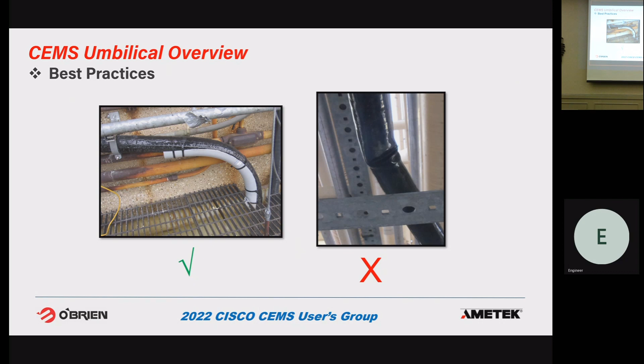These are not great pictures, but this is showing a tubing bundle, and then they've stopped it short. This is an analyzer cabinet. They've got the last 6 inches as bare tube. Bring it all the way into the shelter, all the way into the cabinet. Processed fluids, but especially gases, lose heat quickly. So don't pay all this money on a tubing bundle and end up having that last section not heated. The same reason applies with the zones. You want to make sure you have a complete zone exiting the bundle.